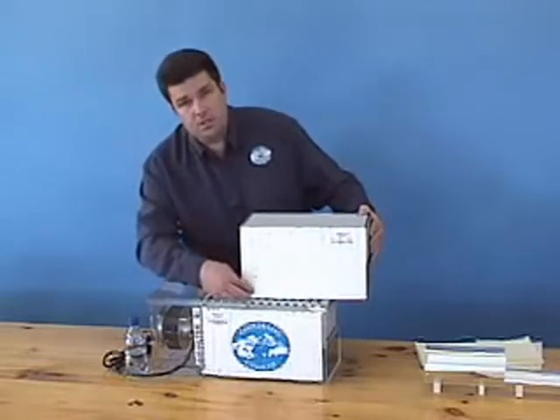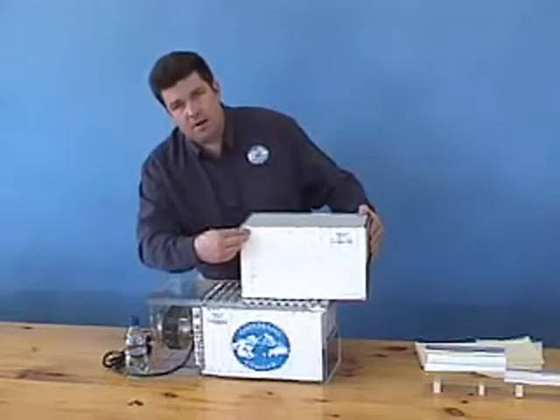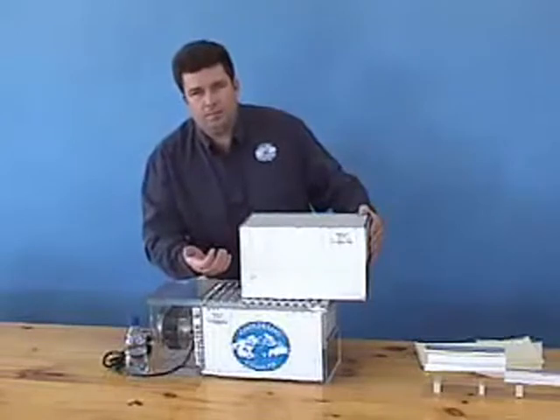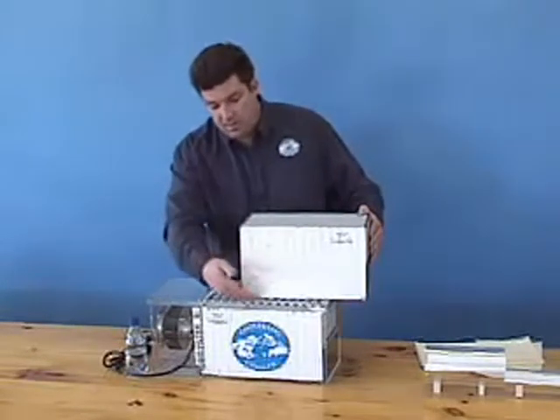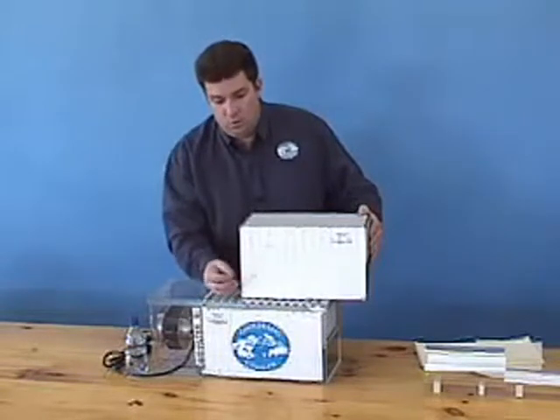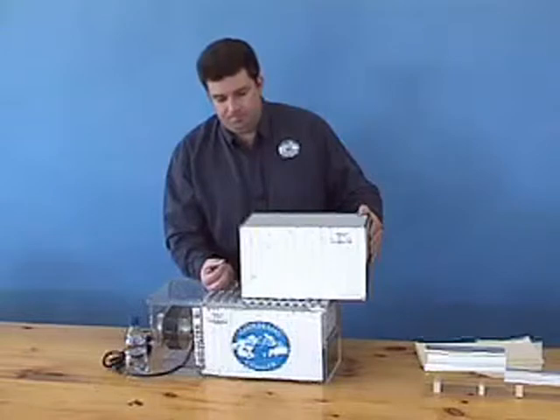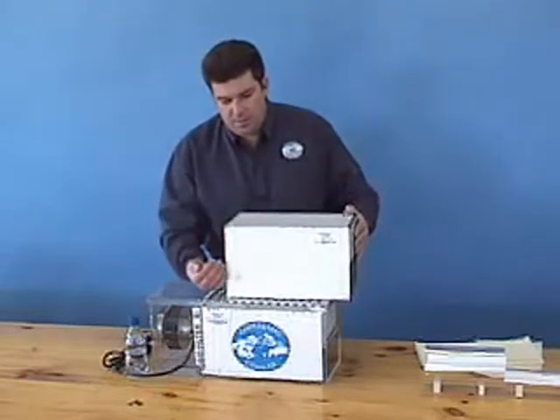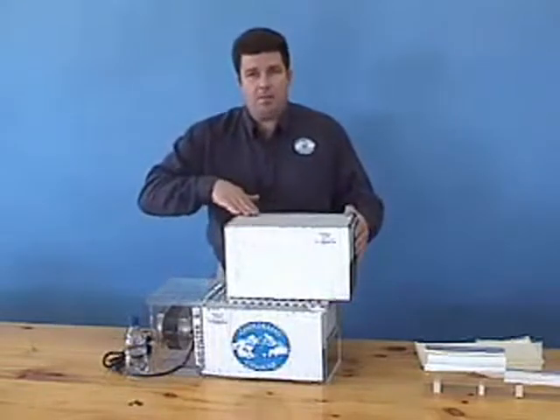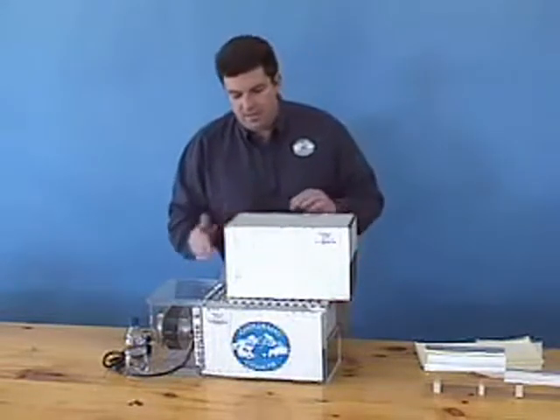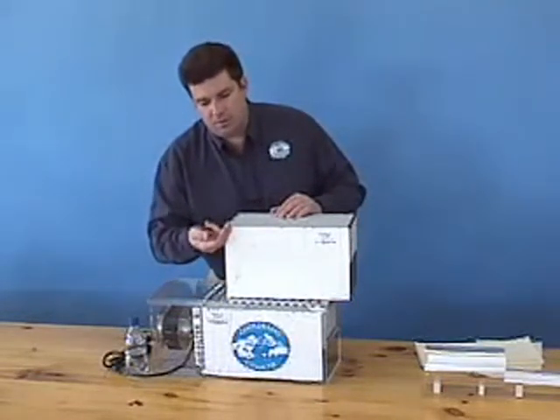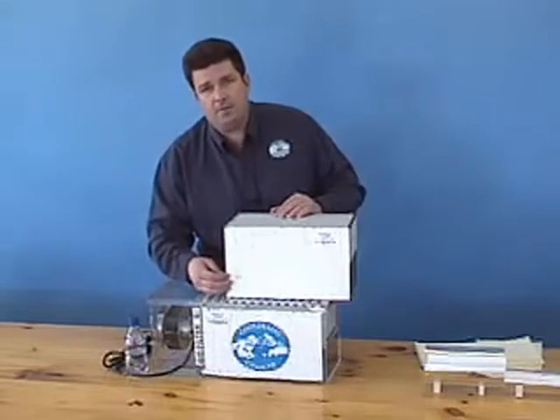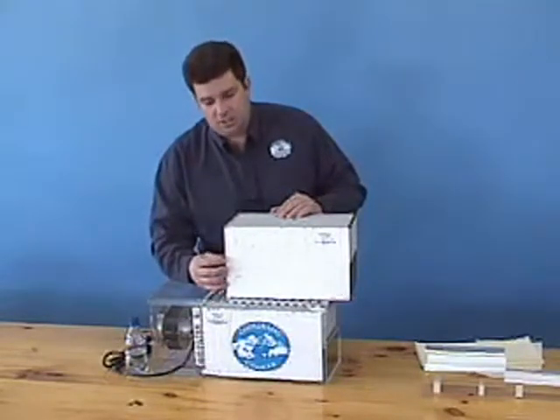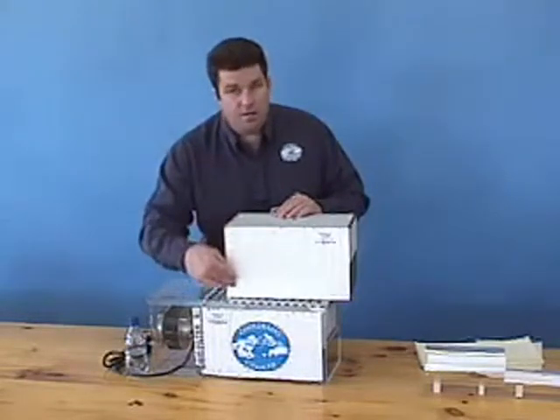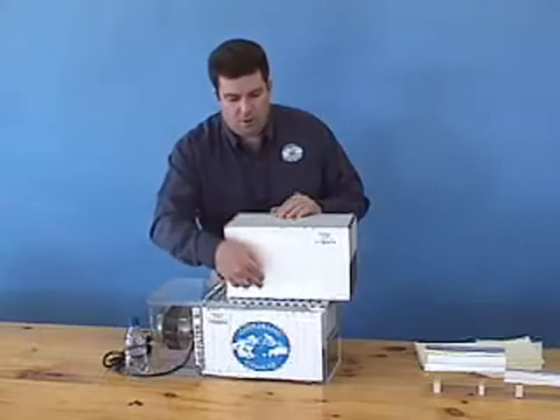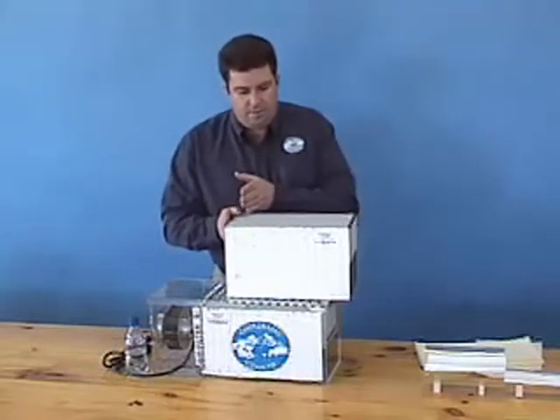Within the first inch, the first 1/13th of air is fractioned off and goes into an adjacent wet channel. The wet channel is wet because it is sitting in a reservoir of water at the bottom and wicks the water up along the length of the wet plate. The wet channel is perpendicular to the dry channel and exits out the top of the heat exchanger. As the first 1/13th of air travels in cross flow to both the working and product air, it takes heat away from the dry channels, from the plastic heat exchanger. This same process occurs another 12 times, incrementally cooling both the product and working air streams as the air travels down the heat and mass exchanger.